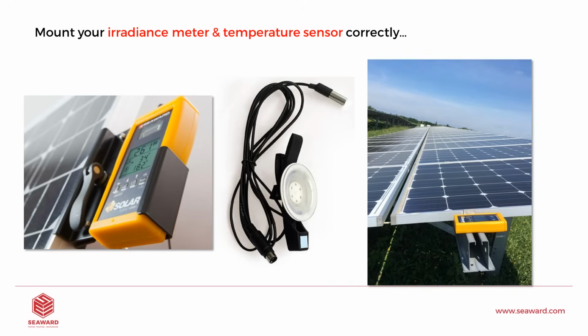We really need to get accurate temperature data in order for us to correct voltage to STC, because the open circuit voltage is directly affected by the cell temperature. So with the temperature probe, for instance, on a 70 cell module, we should go 6 cells down, 3 cells in, and place it in the center of the cell. What this will do is take away any additional heat that may be generated, because if we place it near the bypass diodes of the panel, generally heat tends to accumulate around this area. Also around the framing system, there's a lot of heat that accumulates around the aluminum frame.